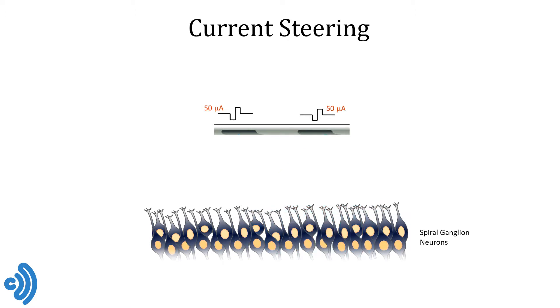So what's going to happen now if we stimulate both electrodes at the same time and with the same current amplitudes? Well, something like this. The electrical fields around the two electrodes add up and if they are sufficiently broad, they will combine into a shape that has its centroid somewhere around the middle in between the two physical electrodes. And this in turn leads to a pattern of neural excitation with its centroid located in between the electrodes as well.